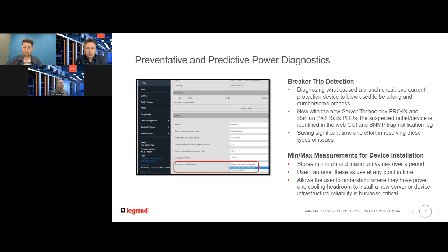But let's just say that the branch circuit's overloaded and the breaker trips, and you get an alert from the PDU that lets you know that's happened. It can be a difficult situation, especially if it's remote or at a colo. But even in a data center, it requires smart hands. Typically somebody's got to go out to the cabinet and determine the branch circuit that actually failed. They would unplug everything from that branch circuit, then reset the breaker, then plug devices back in one by one to understand which device or outlet actually had the problem. And then they would have to deal with the problem.